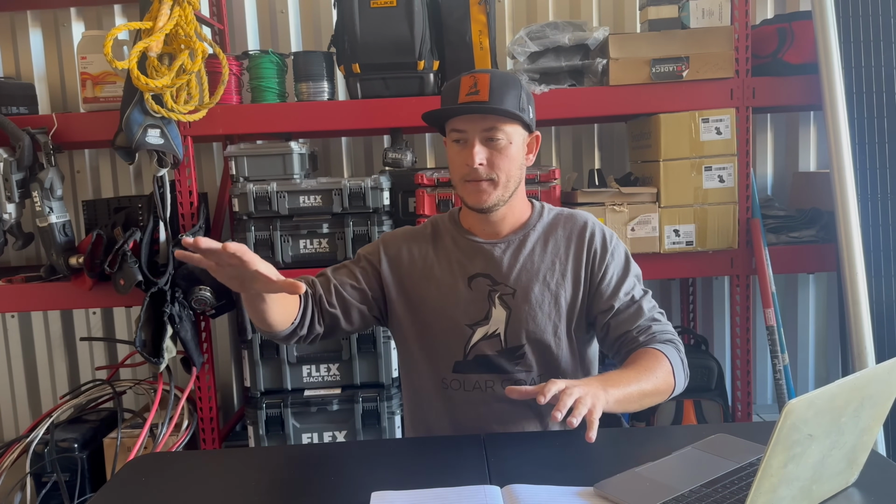If we're looking at the battery connections, we're looking at the solar connections, and we're specifically talking about DC, this is one thing that you need to keep in mind. High amperage, low voltage DC, high voltage, low amperage DC. You're running generally like 12 gauge, 10 gauge, 8 gauge, somewhere in that range, depending on what you're doing on the roof for these 500 volt strings.